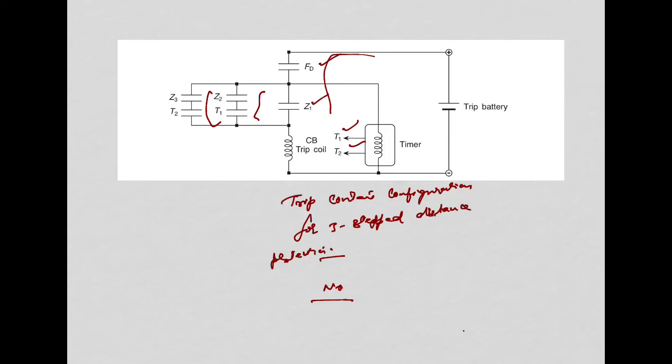Now, the three-step protection for a three-phase line against all the ten faults. We have already seen that three phase fault measuring units, which are fed with the delta voltage and delta currents, and three ground fault measuring units, which are fed with the phase voltage and phase current compensated with the residual current, are required for the complete protection of the three-phase line against all the ten faults. So we already discussed that 6 measuring units are required.